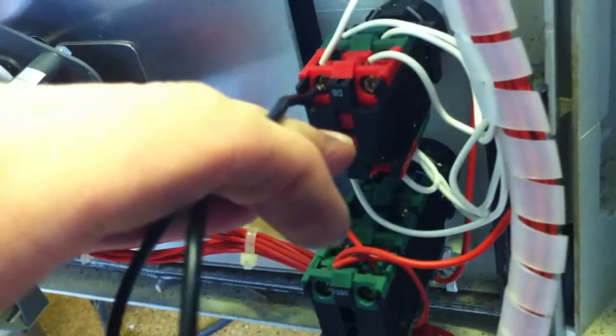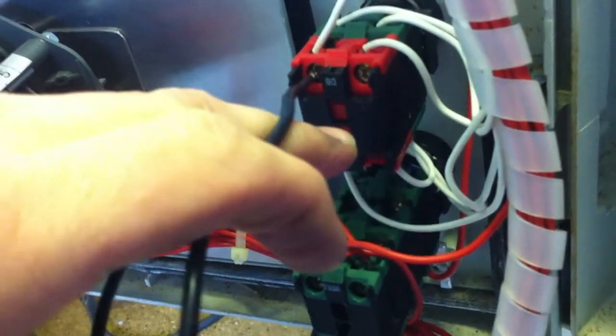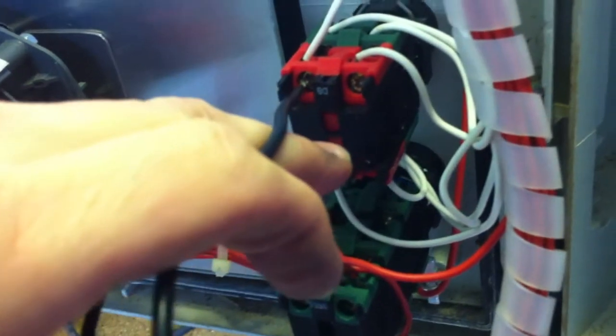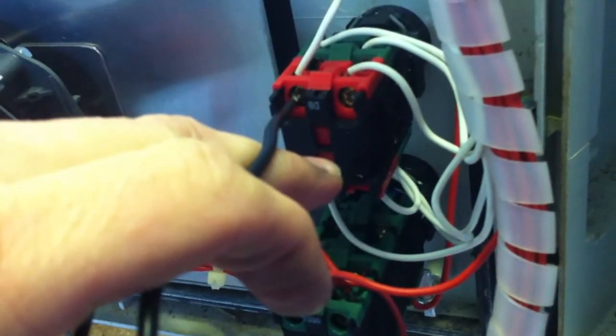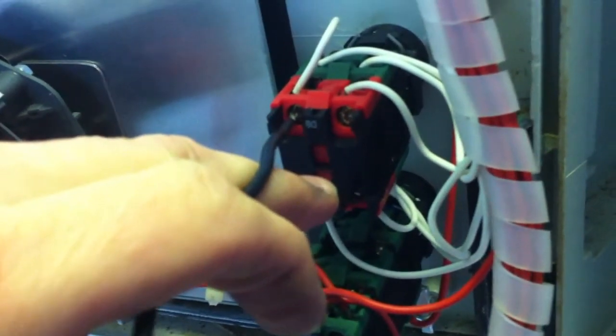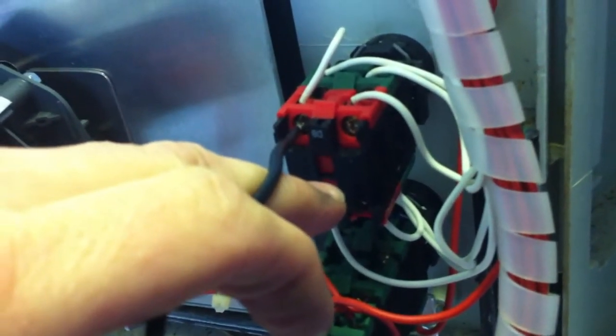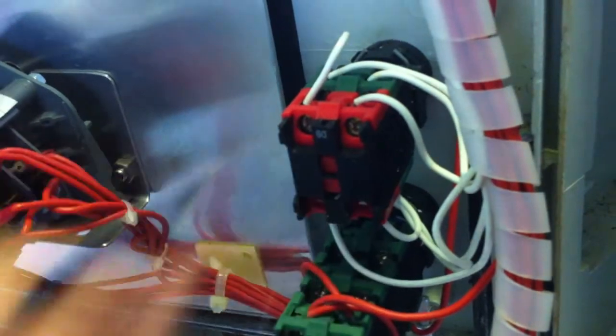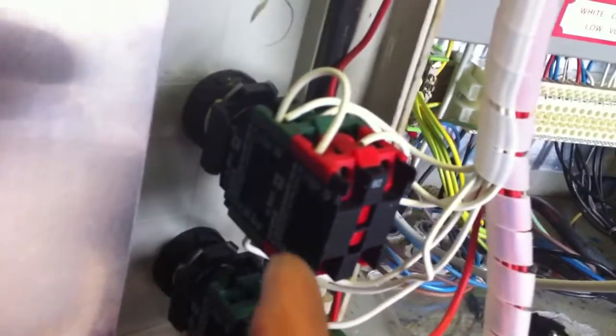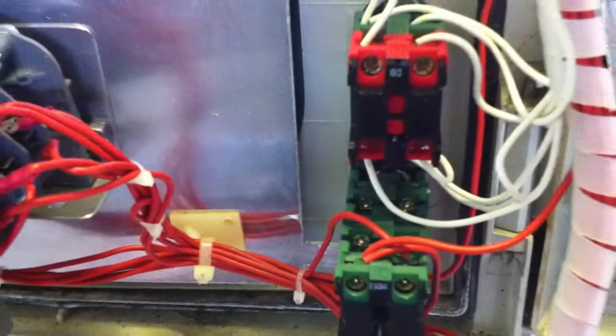I've had these little switches here create problems in the past. So it works here—it's normally open and normally closed. It changes between a small probe and a big probe depending on how much ice you want to make. Because it's only switching about 12V DC with no current, over time the contacts go bad. So that's where the problem is.